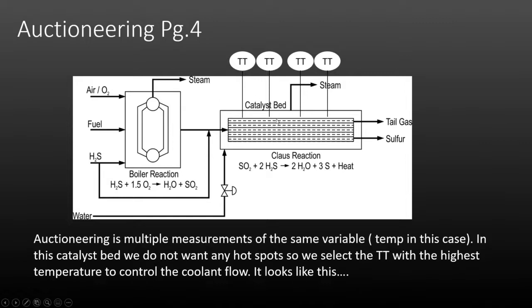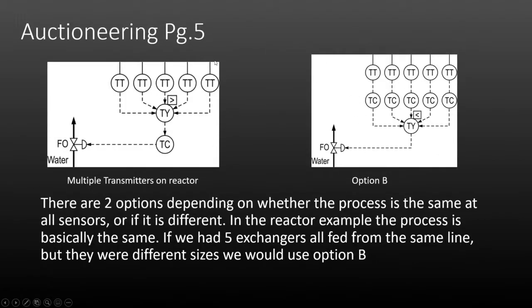We don't want any hot spots that will increase the reaction rate faster than we can handle it, so we select the temperature transmitter with the highest recorded temperature in order to control the coolant flow — this valve that controls the cooling water. There are a couple of ways to do auctioneering: either individual controllers for each transmitter, or one controller with multiple transmitters feeding their information to one selector.